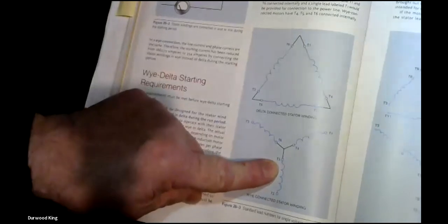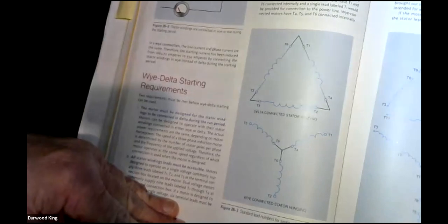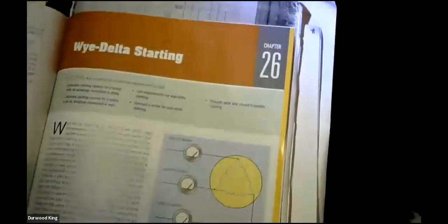And that's what Schindler's doing on their escalators. They're doing this when they don't use a VFD. On smaller motors that are below 5 kilowatt, I believe, I think if they're below a 5,000 watt motor, it's in kilowatts there, then they're doing this. If you get really big ones, then they go with a standard delta motor, and they use a VFD to give you a soft start. They program a VFD to give you a soft start. But again, if you ever need to get into it, it's in this book.